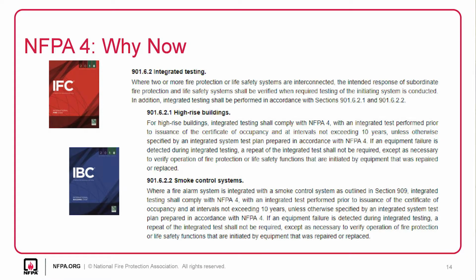Same basic concept. This is the International Building Code and the International Fire Code. I think the text in here is a little easier to understand than the way it is in NFPA. But basically it's saying you need to test the intended response of a subordinate fire protection and life safety system, and the word they use is verified, anytime testing of the initiating system is conducted. So probably their way around that is looking at the initiating system, so systems going into the fire alarm panel, but it doesn't necessarily say anything about the fire alarm panel. And then again, it says for high-rise buildings and buildings with smoke control systems, you have to follow the requirements per NFPA 4.